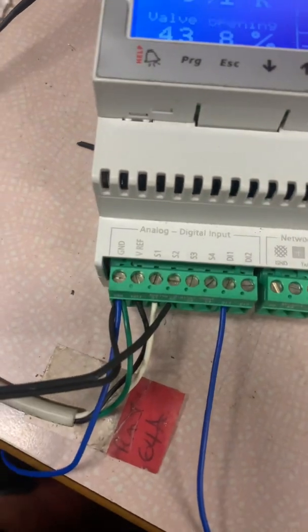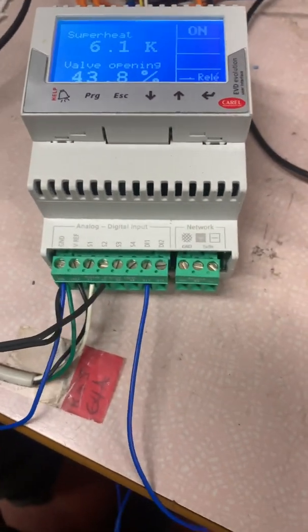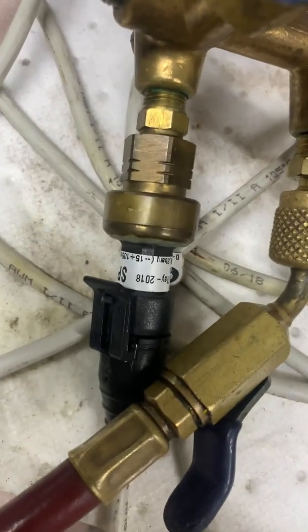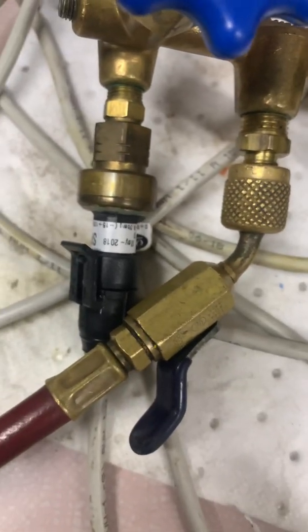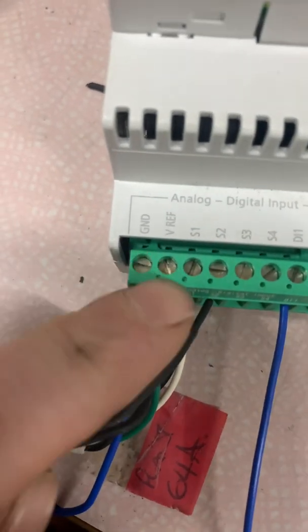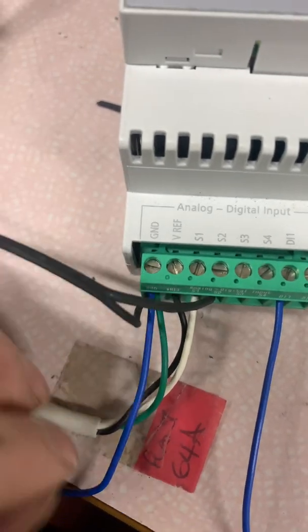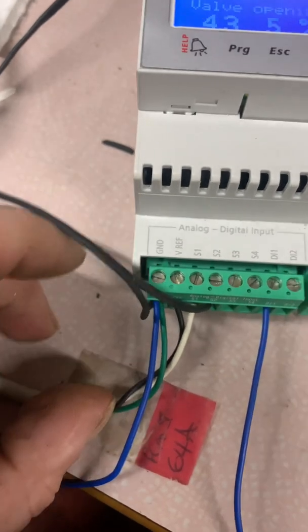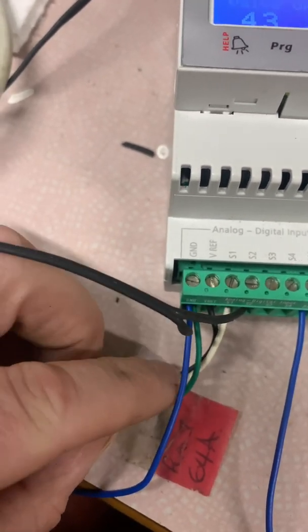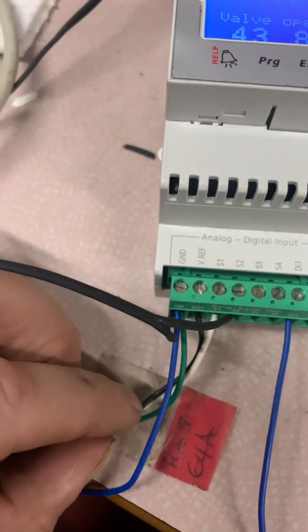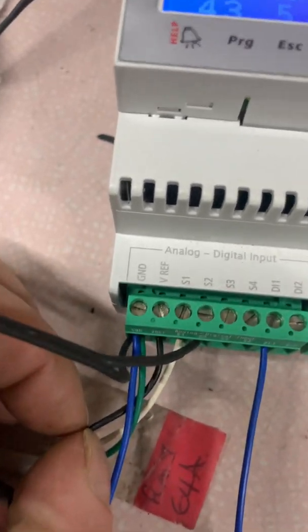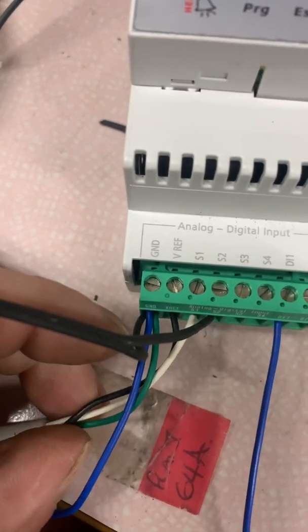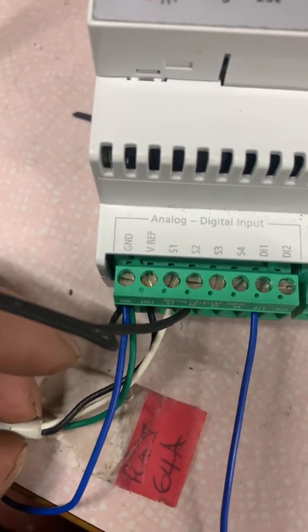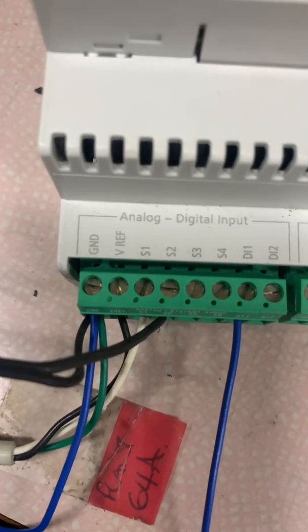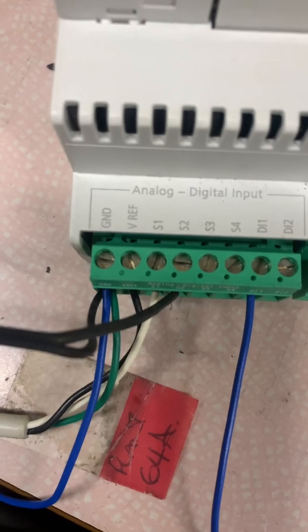Then at the bottom we've got the connection to the transducer that comes with it, which you've got to have the right transducer, the Carel one. So it tells you the connections there. We've got green as ground, black as the voltage reference, and then the feedback is going to S1. So that's going to be your reading from your transducer.